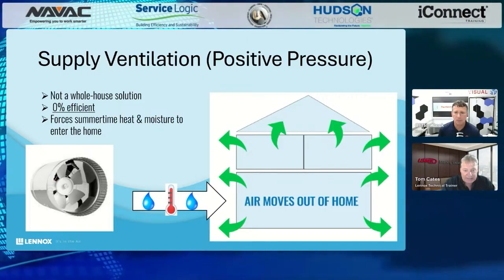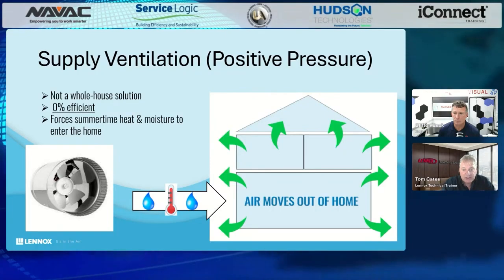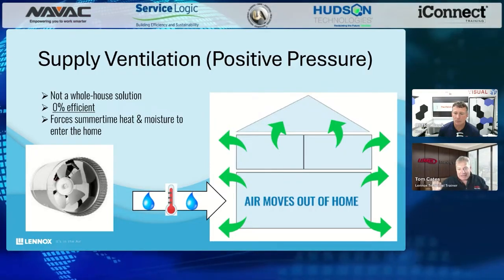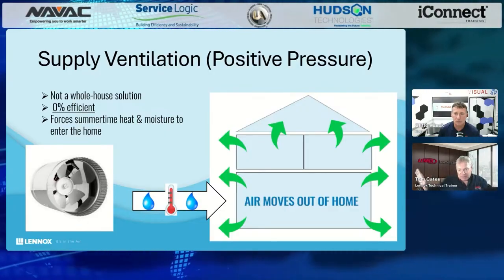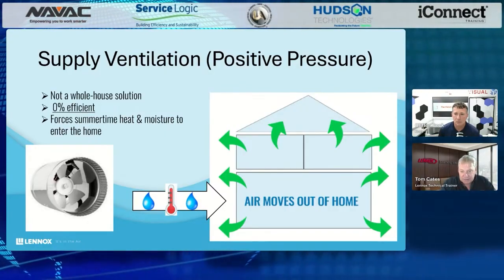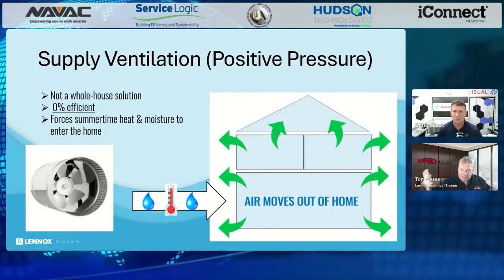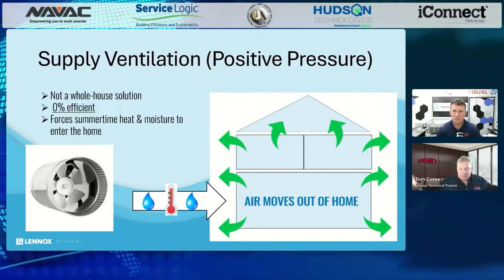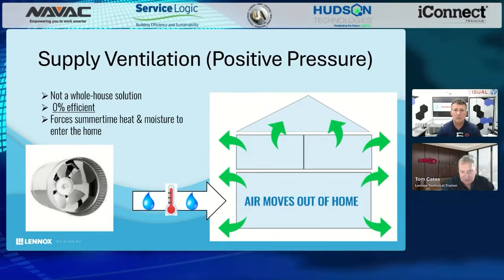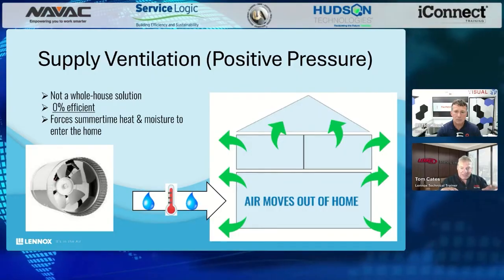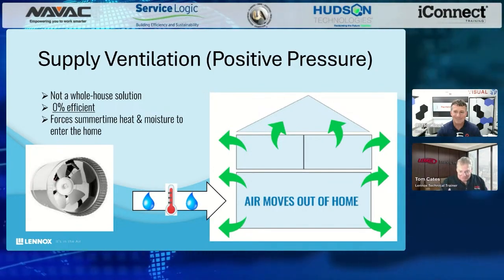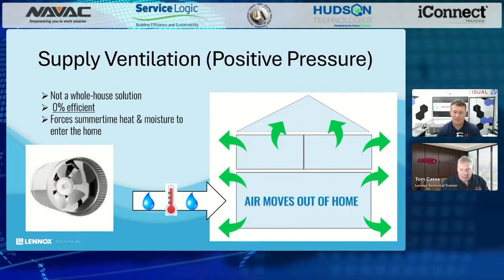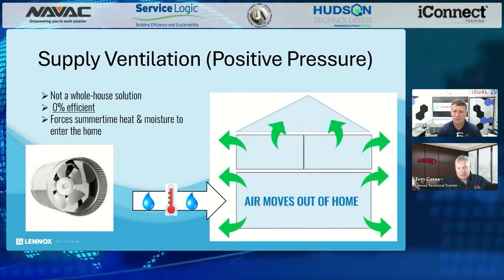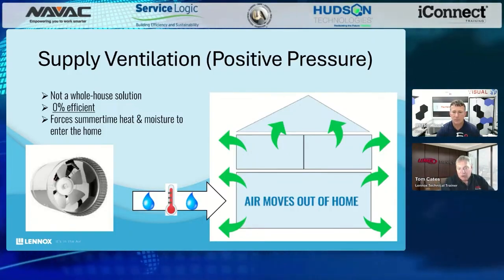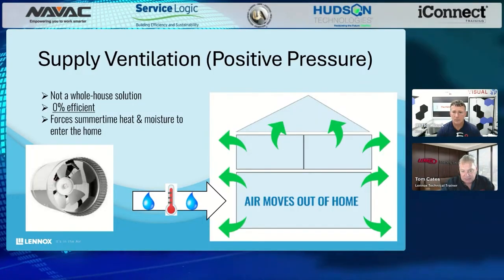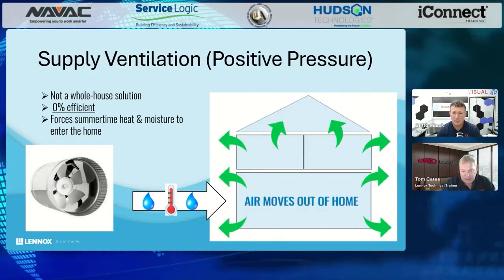Makes sense. When you get down into the southern parts of the U.S., however, they might choose to do the supply only because now we're trying to keep that moisture out of the building. I think about the summertime in Florida where it's 60 or 65% relative humidity. By pressurizing that building, I'm pushing the air out of it as opposed to letting it come through the building envelope. And so again, we're going from a conditioned to cold condition house in Florida, and we're pushing that to an outdoor warm exterior. So as that air moves through the building envelope, it actually has a drying effect as opposed to a moisture generation effect that we would see here in Canada.